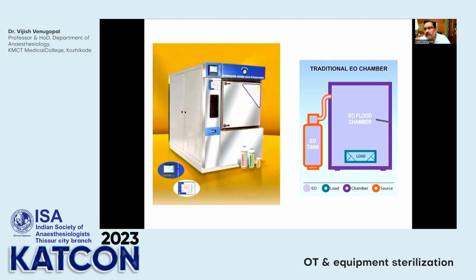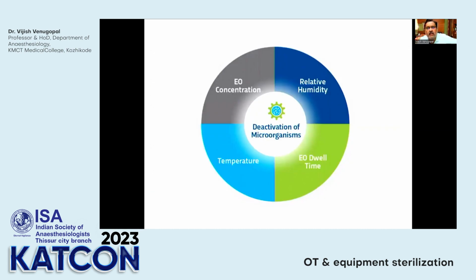The other classical technique is the ETO, which all of us are using. And we have these huge ETO chambers, and there is an ETO tank which floods the ETO chamber, and where the load is, it gets sterilized. Now, ETO is a poisonous gas, so we should use all precautions when you use ETO. And it's an odorless and poisonous gas, and the deactivation of microorganisms depends on the ethylene oxide concentration, the relative humidity, the dwell time, and the temperature.